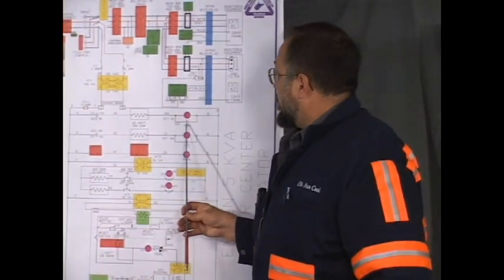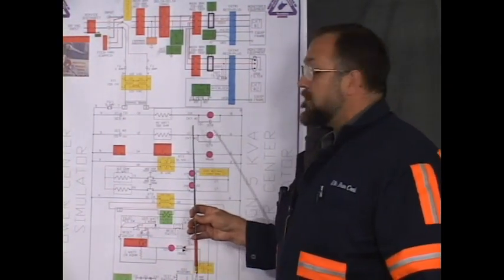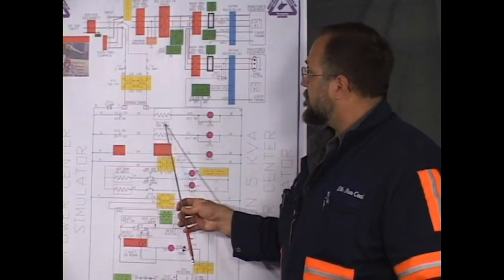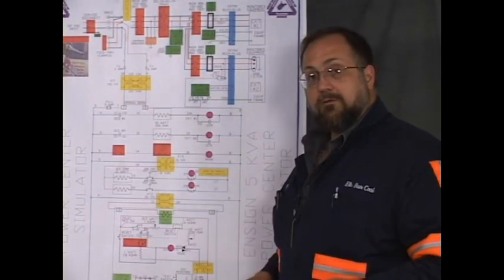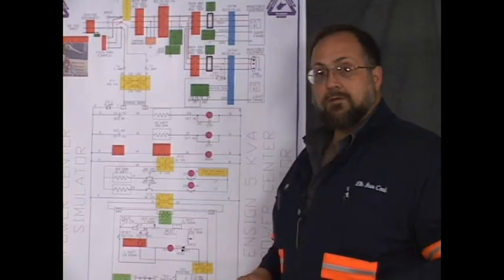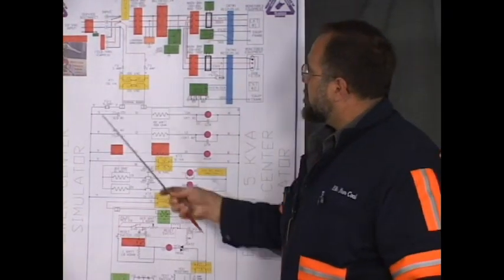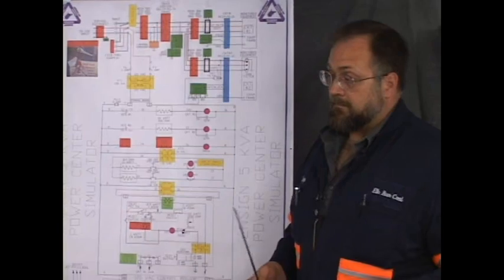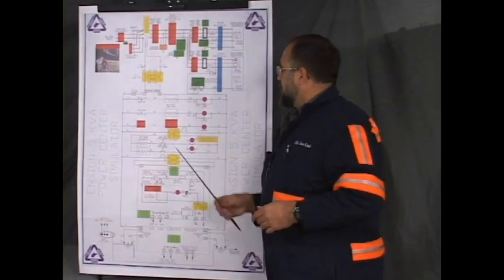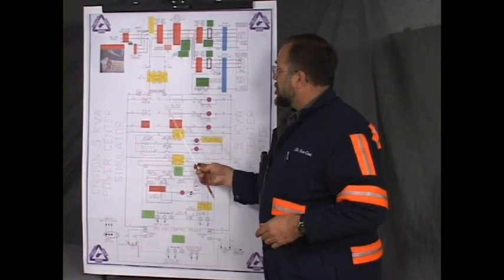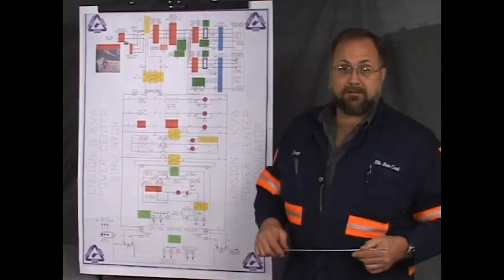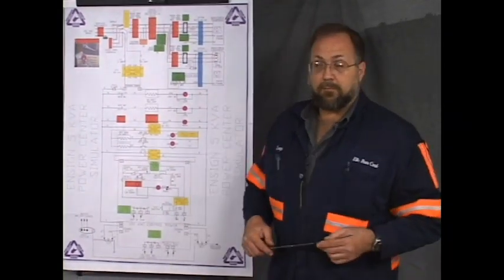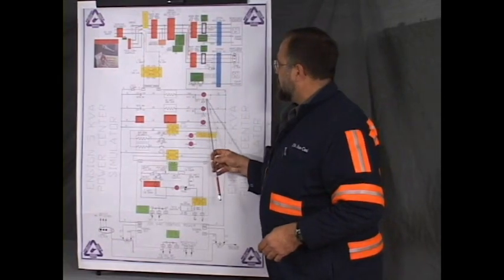Anytime that the ground trip relay contacts closed, whether you had a fault or you had pressed the test button, anytime these contacts closed, it would make a short circuit. This resistor is there to provide a load to limit the current to avoid blowing this fuse. Well, there's only two problems that could cause all the voltage to be dropped across that resistor and that condition to be sustained. Both of them involve the closing of these tips.